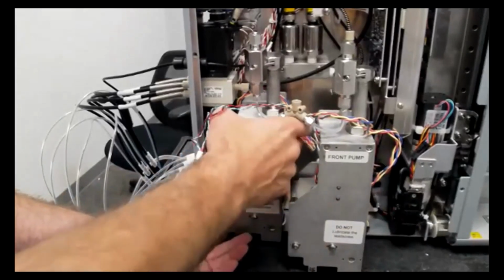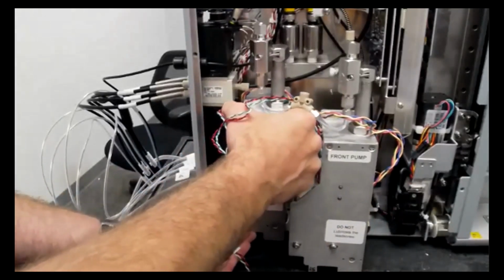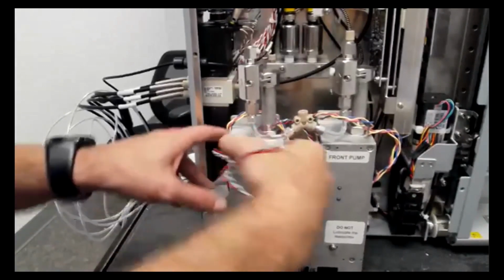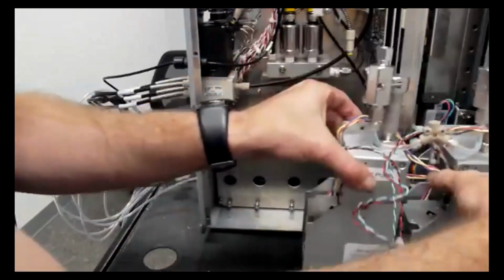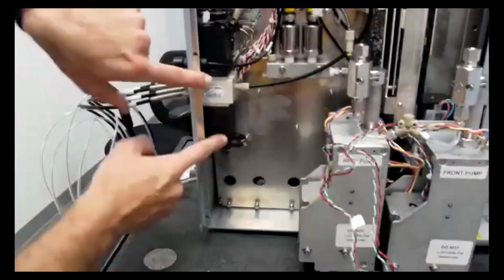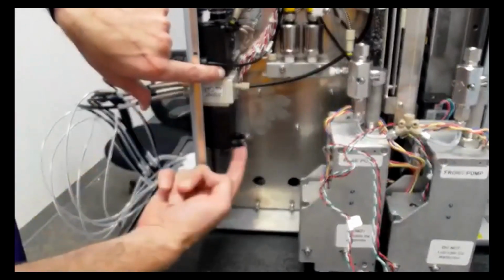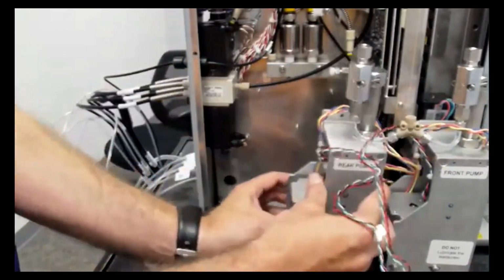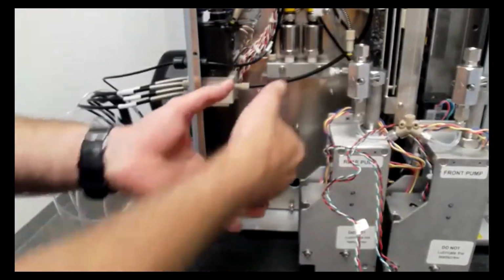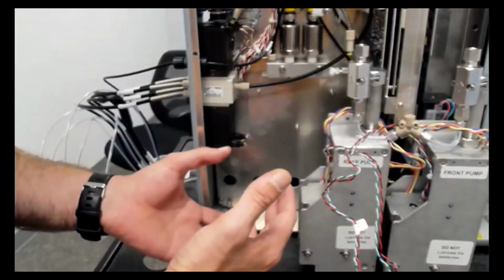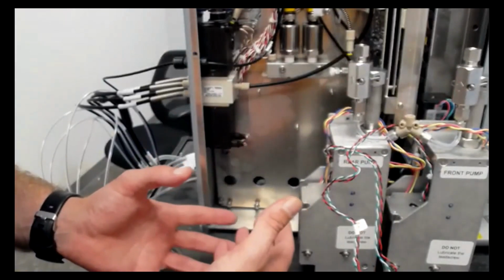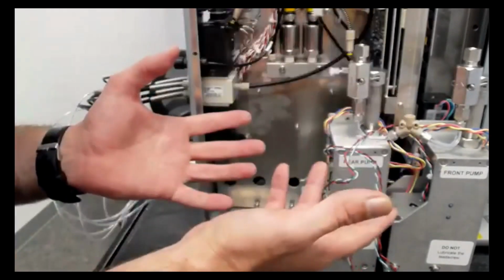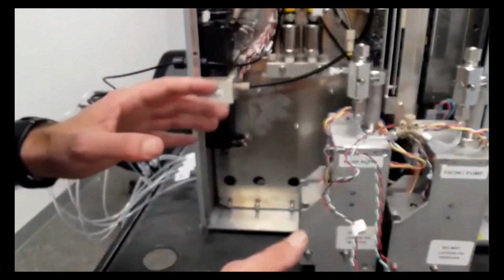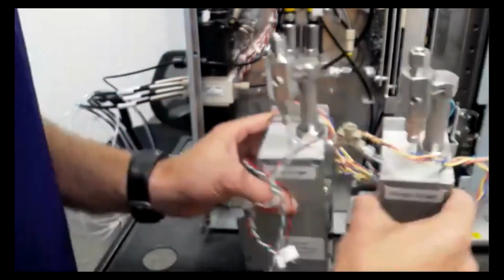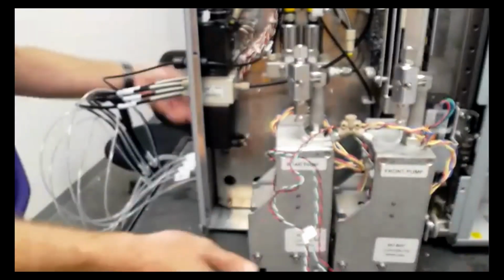So I pull forward, and you want to lift up just a little bit. Be careful. They can come out. Be careful of your solvent select valve here. There's these connectors that can catch on this pump as you take it out. Patience is a virtue, as I keep saying. So do this stuff slowly the first few times, and then you'll be a master. And you can do everything that I'm doing here in like 20 minutes, okay? But now those pumps are out of the way and they're ready to be serviced.